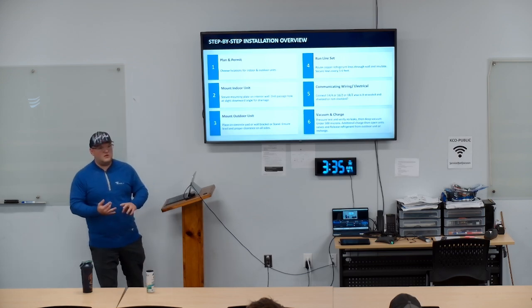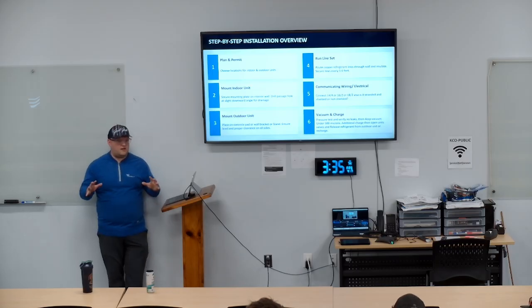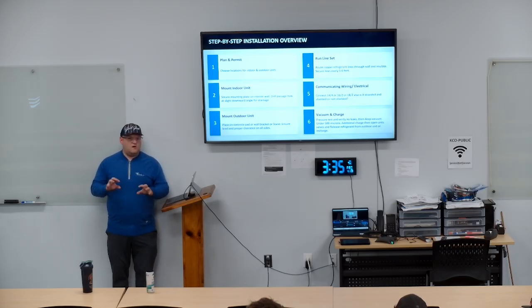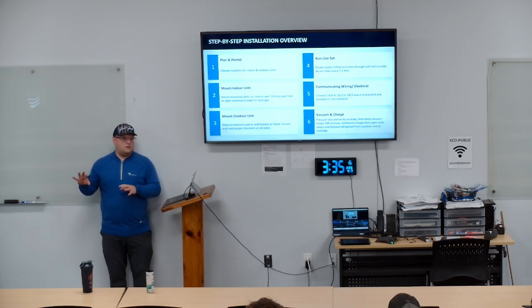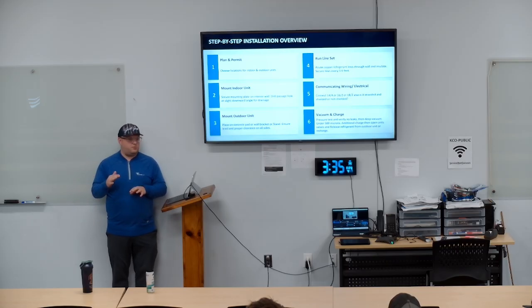So with these A2Ls, with the new refrigerants and all this stuff coming down the line, how much more communication things they're putting in there with leak detection systems and all this kind of stuff. I'm seeing way more communication wire coming off of splits now than I am just a 14-4. The only one that seems to have it mastered, that they'll let you run 14-4 to anything they have, is Mitsubishi. But we don't buy that because no one wants to pay an arm and both their legs, and it's normally priced high, but we love them.